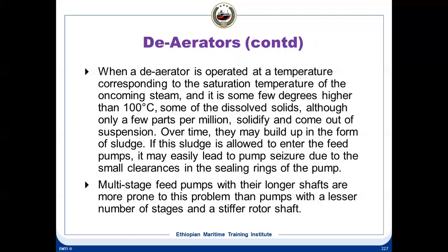Normally in steam, there should not be any solids, but in case some solids are coming from your heating coils, from your turbines, etc., some scale has got dislodged and has got dissolved in the condensate. Even though the concentration of these dissolved solids will be very little, they can come out of suspension and solidify, and over time they may build up in the form of sludge. And if this sludge is allowed to enter the feed pump, it can lead to feed pump seizure due to small clearances in the sealing rings of the feed pump.